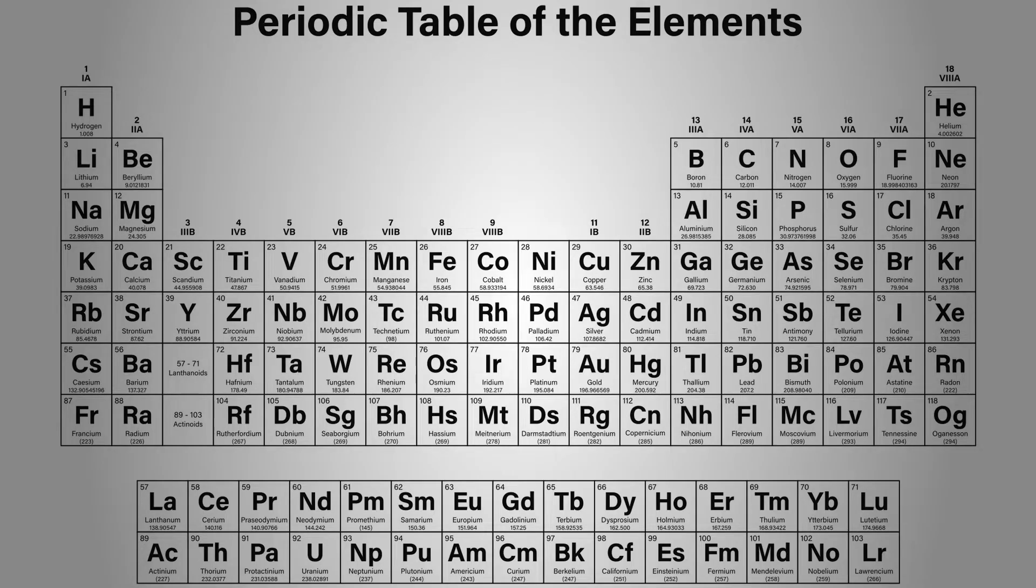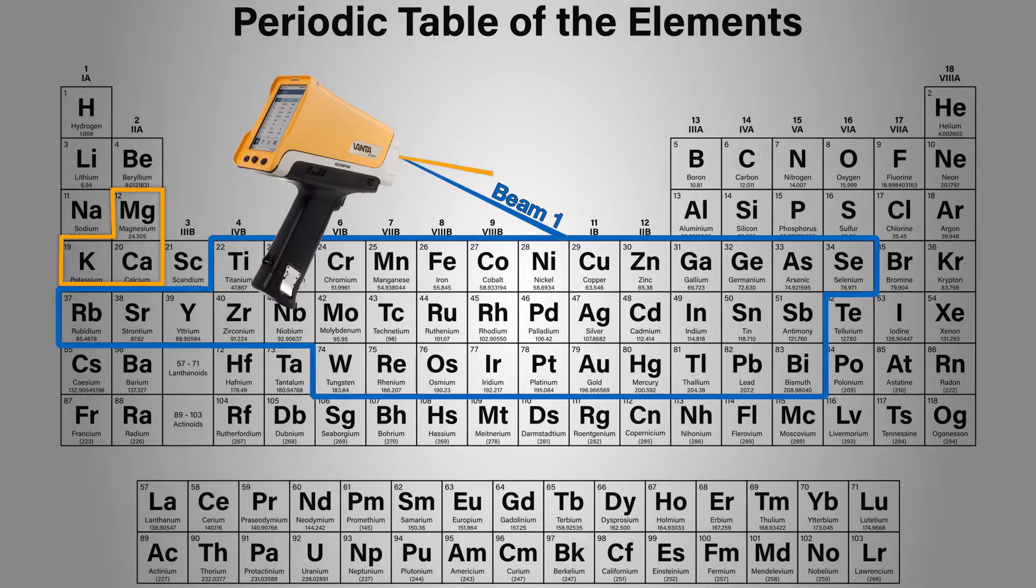Sure. What's a beam or a beam setting? Using different beams allows us to optimise the instrument for different parts of the periodic table.